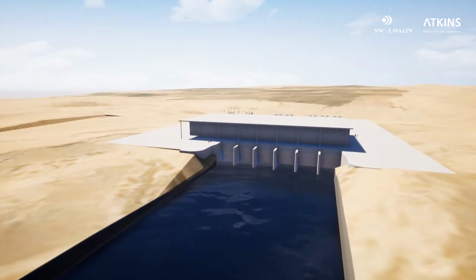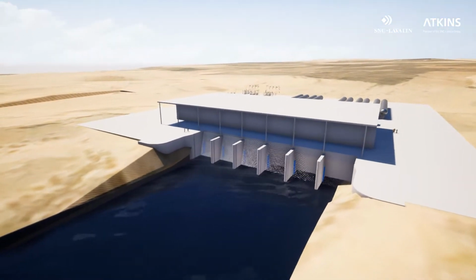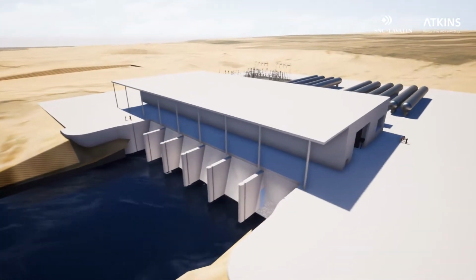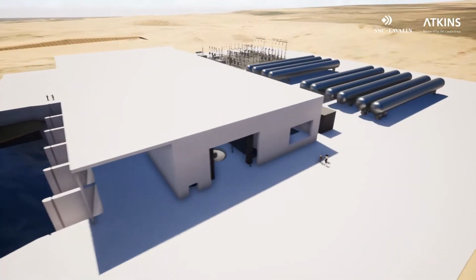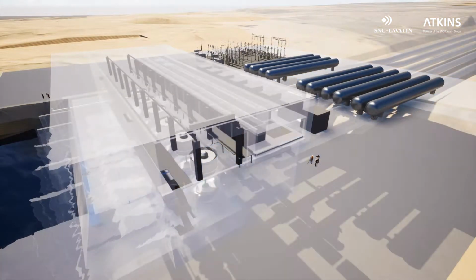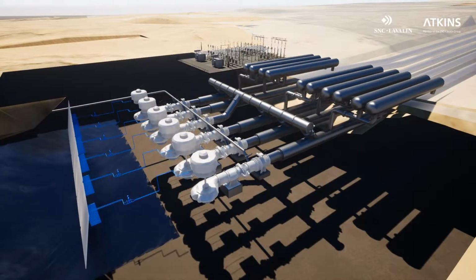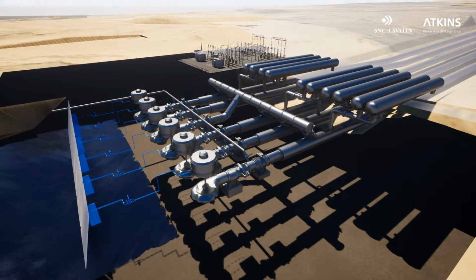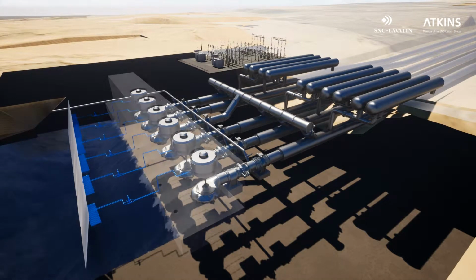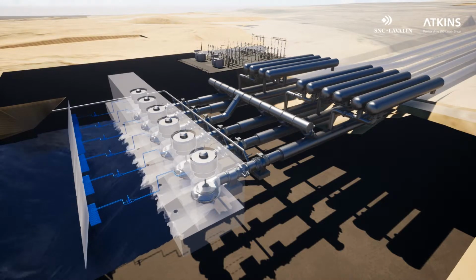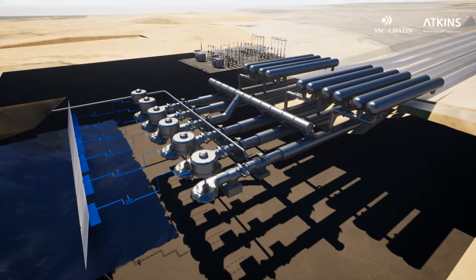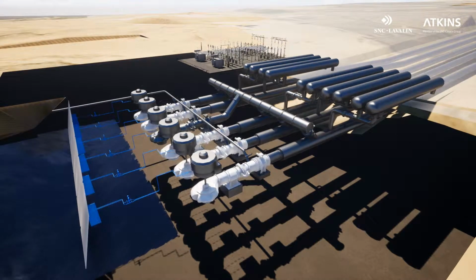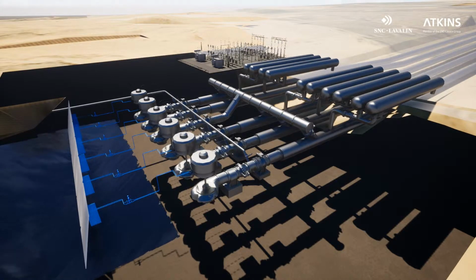A gigantic pumping station will lift the water from the level of 16 meters up to 135 meters. This state-of-the-art pumping station design utilizes 6 large volute pumps to achieve the flow with 5 duty and 1 standby pumps. The pump volutes will be manufactured in steel and will be further encased in reinforced concrete, to provide additional anchorage for the high forces which reduces vibration. Each pump will deliver 40 cubic meters per second to a dedicated rising main through non-return and isolation valves.